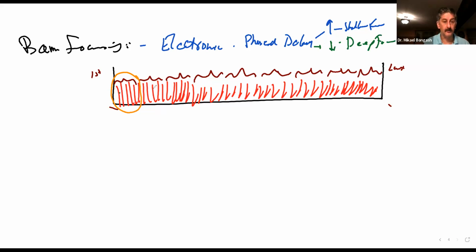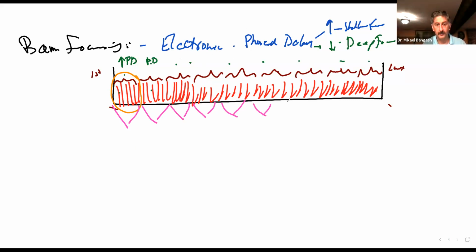But here that is going to be for each group, and they all have the same kind of phase delay. So if in group A we had a great phase delay, that great phase delay was going to be equal and the same for all of the groups. But each group would then form a beam. Like here, a great phase delay would be focused at, let's say, a shallow depth. But that focal depth of the beams produced would be the same.